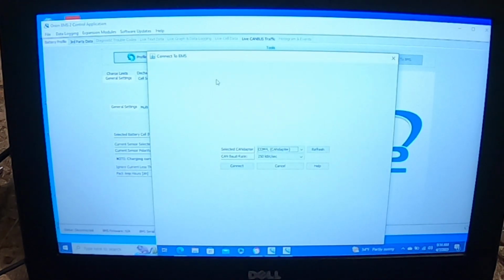All right, so I'm going to connect up to the BMS right now. Also a note, out of the box the baud rate is 500 kbit for the thermistor expansion and also the BMS controller. In this case, I'm using Elcon chargers that I need to talk to over the BMS, and those are hardwired at 250 kbits. So everything on the CAN bus is at 250, so I need to change this. Default would be 500; I'm going to change that to 250 and then connect up.